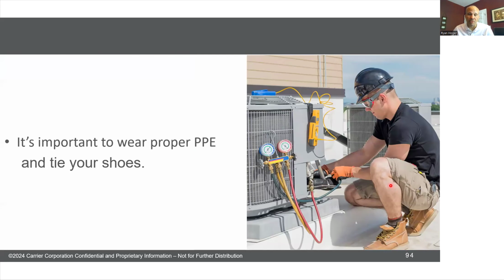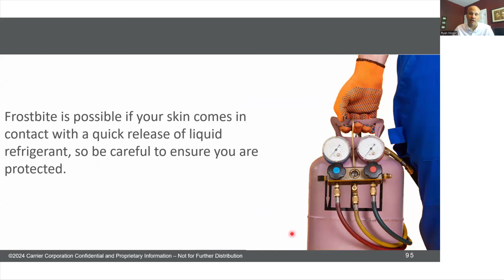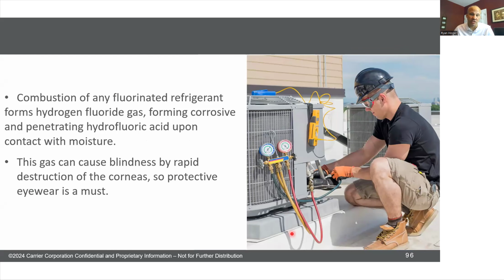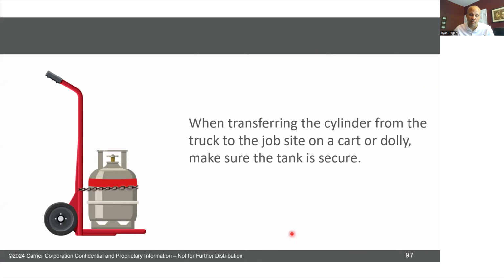You got to wear the proper protective equipment. I know this picture is horrible because this dude's wearing shorts and stuff like that. But you need to wear gloves when you're working with refrigerant, any refrigerant, and you need to wear safety glasses. Maybe not full on goggles like this guy, but refrigerant in your eyes can cause problems. Refrigerant freezing your hands causes problems. These are not new things that you were unaware of. You already knew this. I am just reminding you. Right? Refrigerant causes frostbite, surprise, surprise, and it can cause blindness in your eyes. So that's just a refresher on that information.